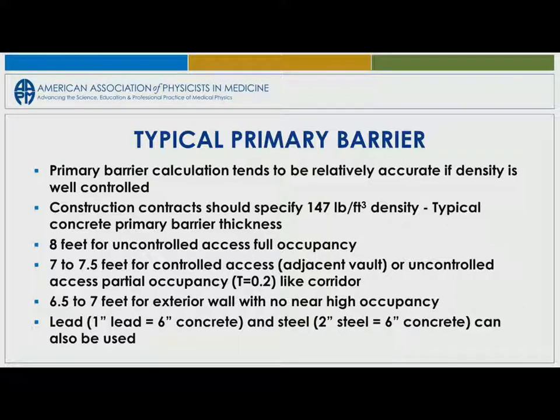If you're doing estimates, default to 8 feet for your primary thicknesses if you have full occupancy, uncontrolled access. In other words, if you're dumb enough to put the secretary outside the primary barrier, that's what you would have to shield it to. Okay, but you can default to these values and at least it'll get you in the right ballpark for getting estimates.